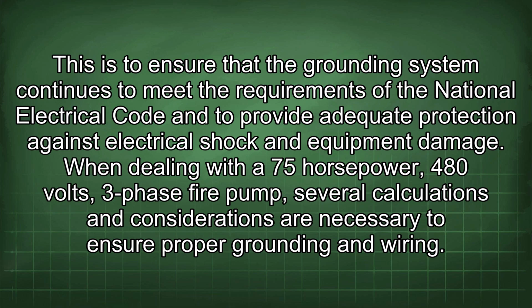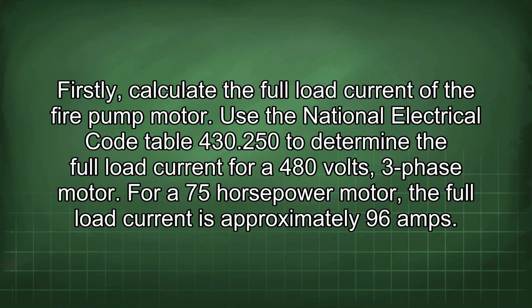When dealing with a 75 horsepower, 480 volts, three-phase fire pump, several calculations and considerations are necessary to ensure proper grounding and wiring. Firstly, calculate the full load current of the fire pump motor. Use the National Electrical Code Table 430.250 to determine the full load current for a 480 volts, three-phase motor. For a 75 horsepower motor, the full load current is approximately 96 amps.